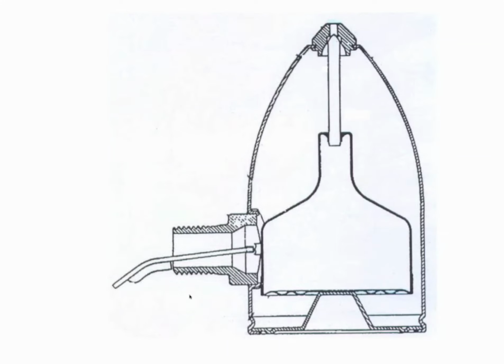This is a very common air vent that's made by Hoffman Specialty. It's called a number 40, and I show it to you because there's so many of them out there. Now, it's got this little piece that sticks inside the radiator that is appropriately called a tongue. And the tongue is there to let the condensate that gets stuck in the trap in the radiator vent drain out. It just dribbles along the bottom of the tongue back into the radiator.